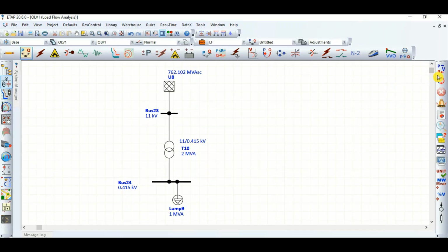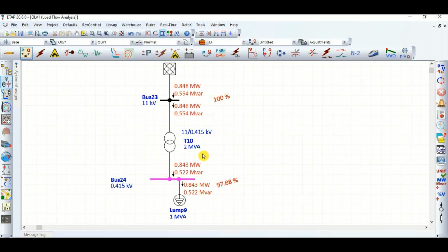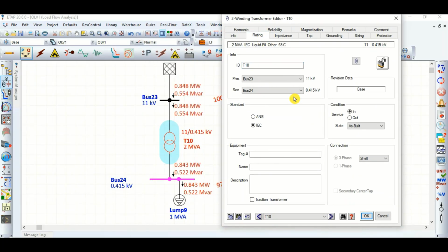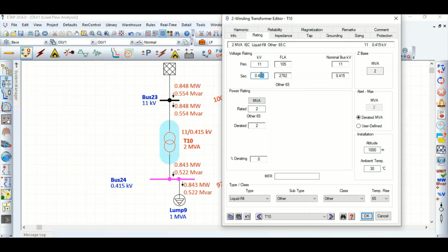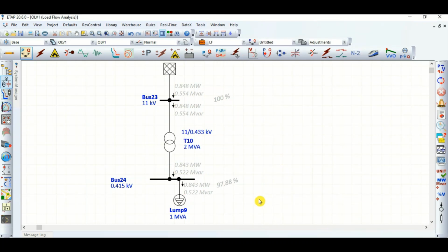So let's run this load flow. As you can see, the bus voltage at LV level is 97.88 percent. Now if we consider this transformer secondary side no load voltage as 0.433 kV, without changing any other parameters, let's see what will happen. Now the bus voltage has increased to more than 100%. Now it is 102.1%.